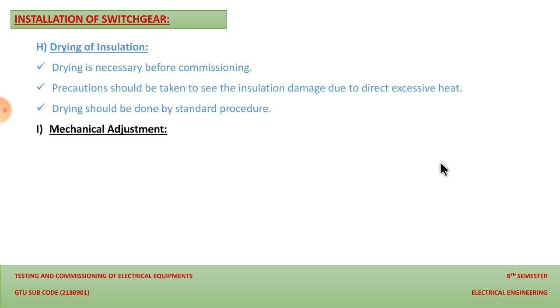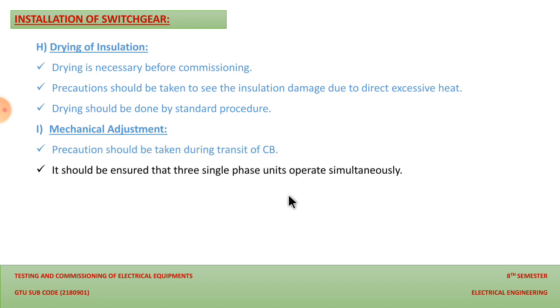Then mechanical adjustment that we need to do, that is, precaution should be taken during the transit of the circuit breaker. So yes, that provides an additional protection for the circuit breaker if the accessories are mounted to the circuit breaker, and during transit it might get damaged. So that precaution should be taken during the transit of the circuit breaker. And the delicate accessories should be sent separately to avoid such damage during the transit.